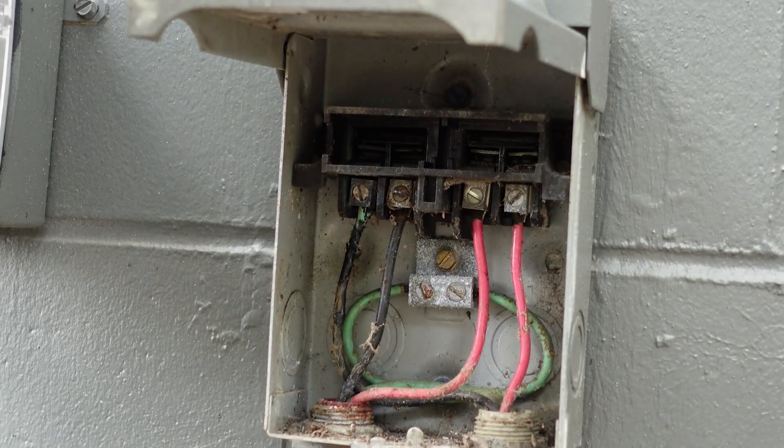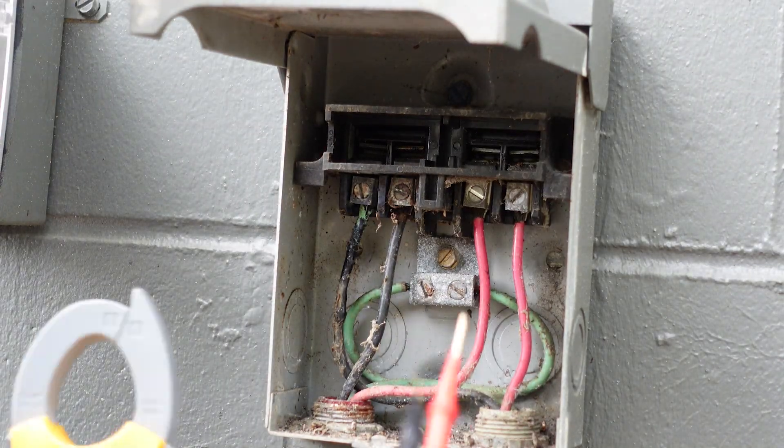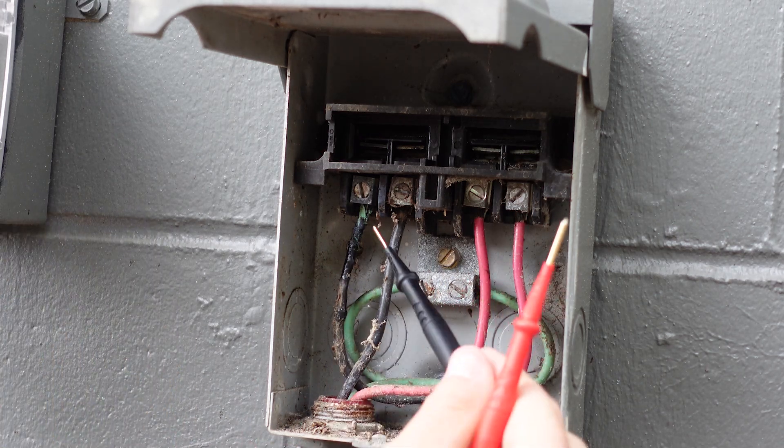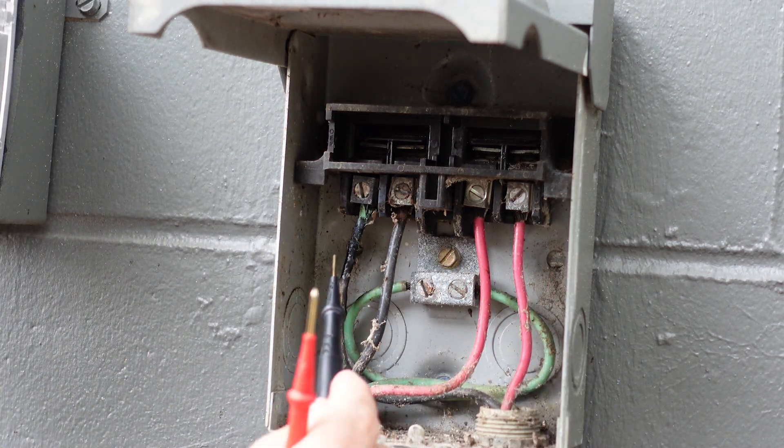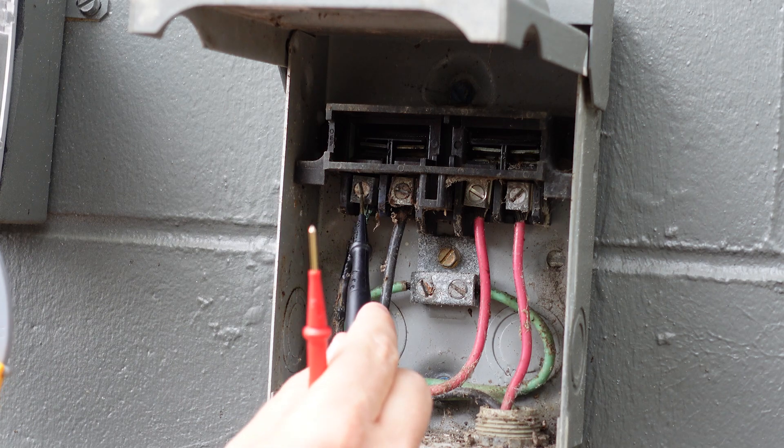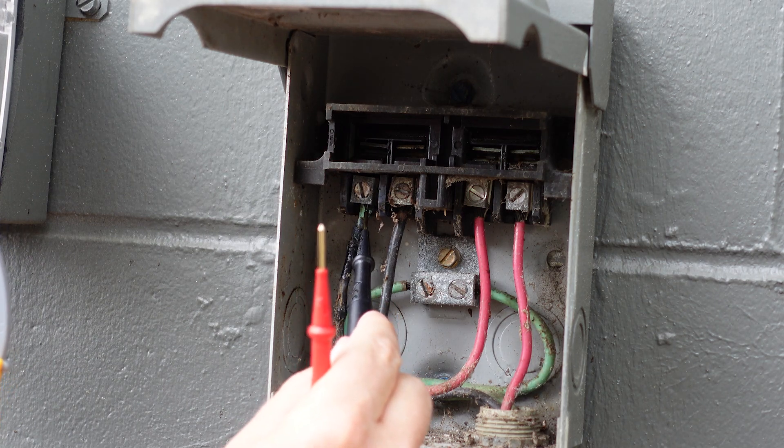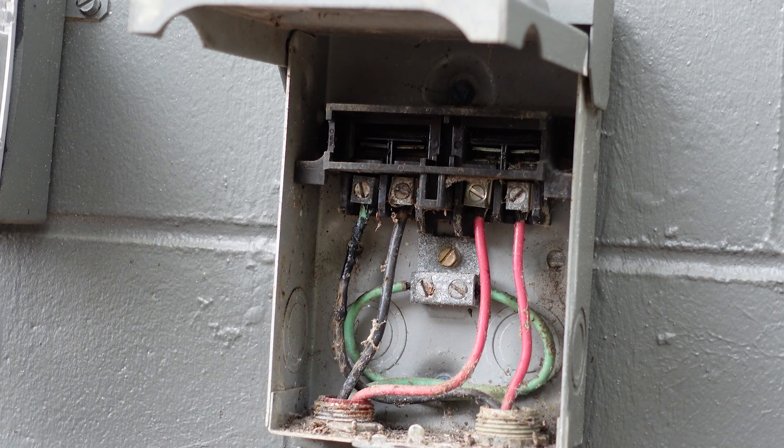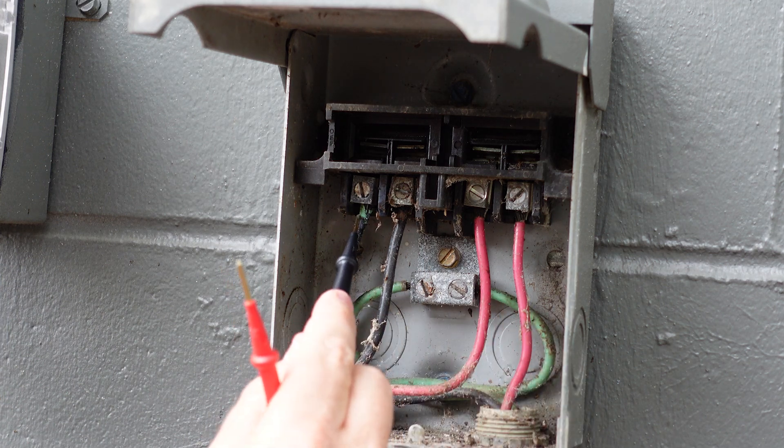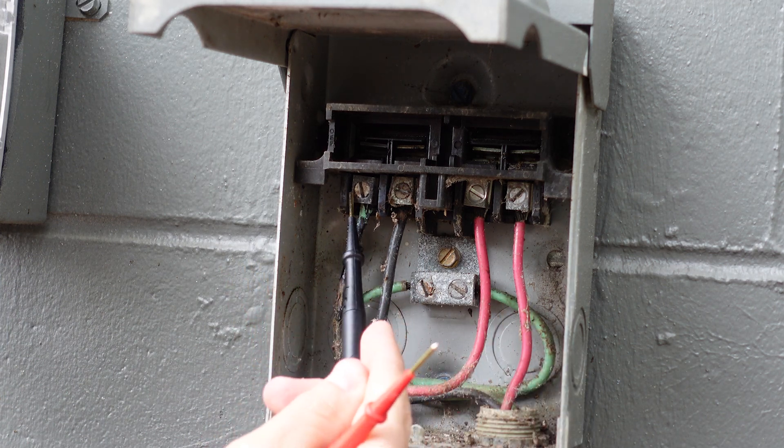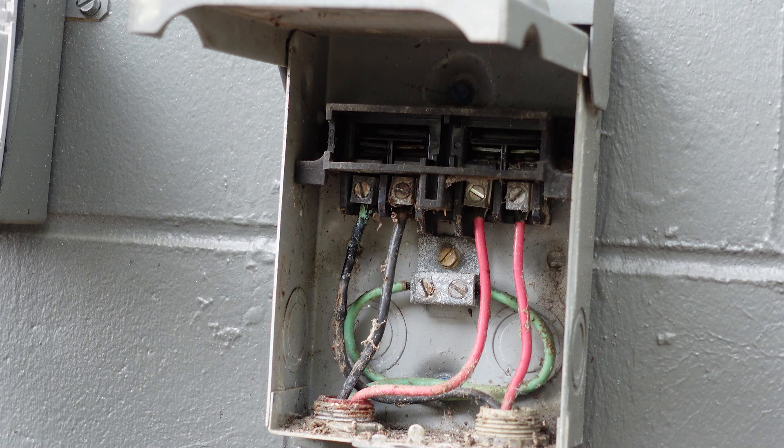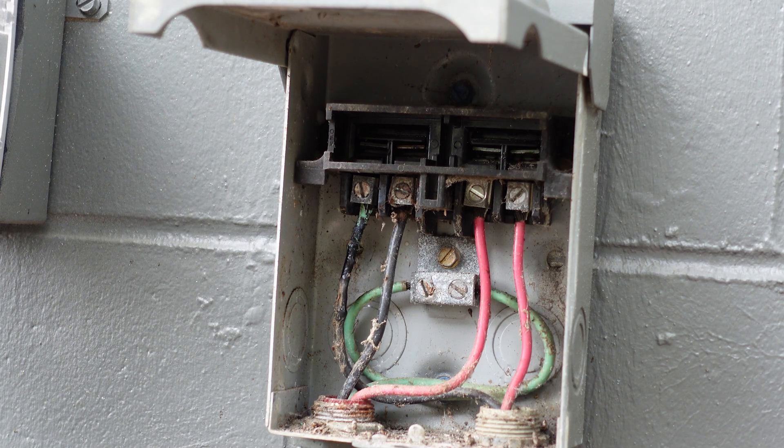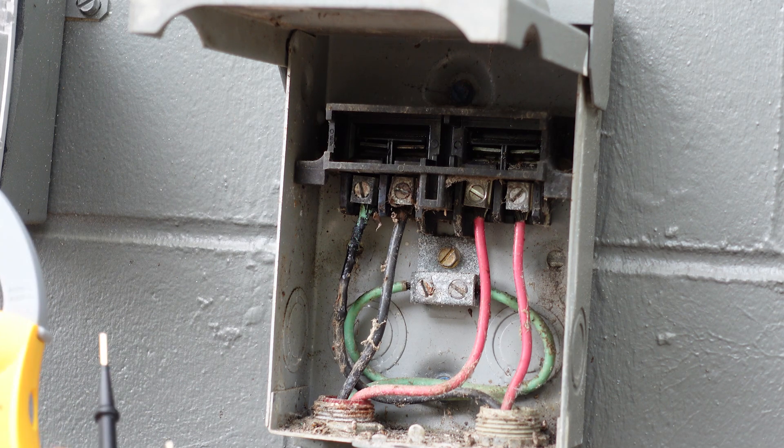I wanted to open this up to show you the tests that we do for safety to make sure that we don't have voltage applied. And what I found was our high voltage wire coming in on this side is all corroded. That connection needs to be completely remade. Probably go ahead and just replace the disconnect because you can see how overheated and melted this is. We're going to actually replace this at a later time. This is just from our office unit.